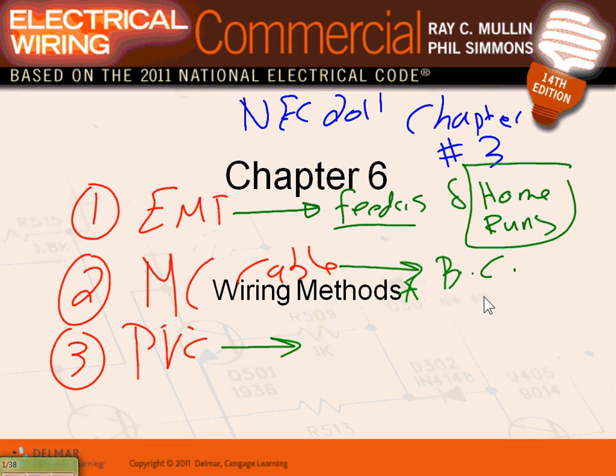PVC conduit, your option number one, guys, is underground. The only place you're going to be using PVC conduit, think about it, is underground. If you don't have an underground or wet location, don't think of PVC conduit. Always think EMT. I want you to focus on these three wiring methods. EMT everywhere else, especially feeders, especially home runs. MC cable everywhere else for branch circuits, from the first J box into all the conductors.